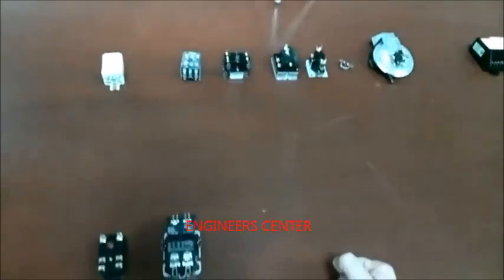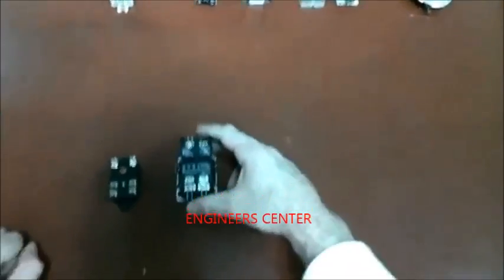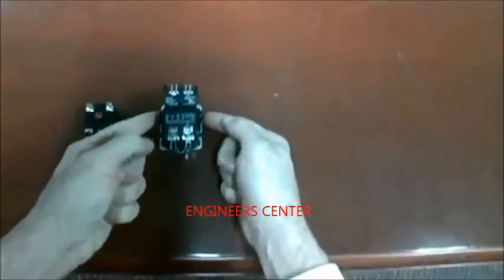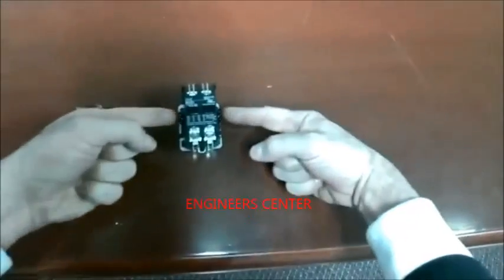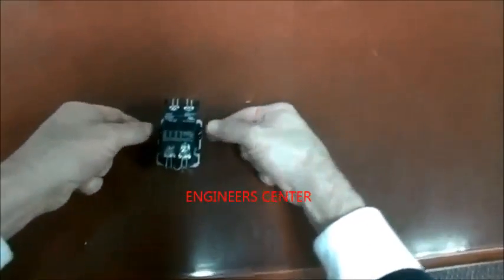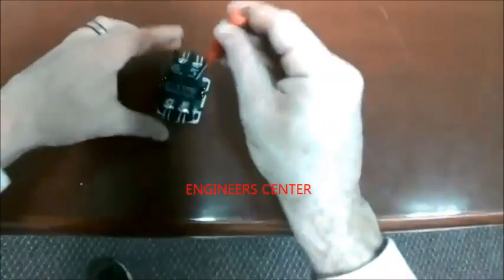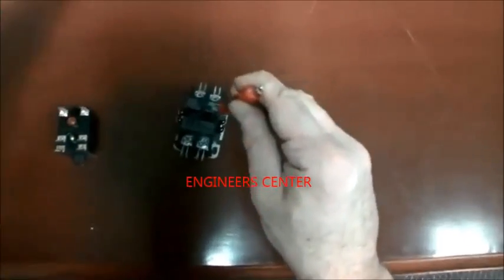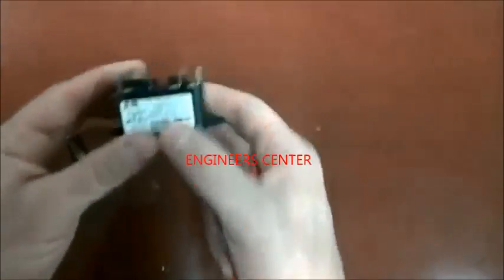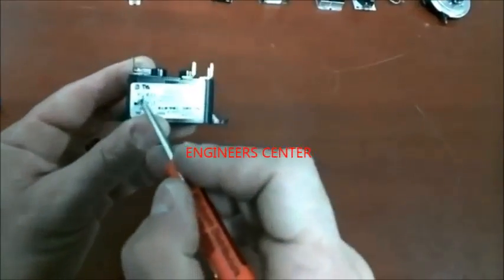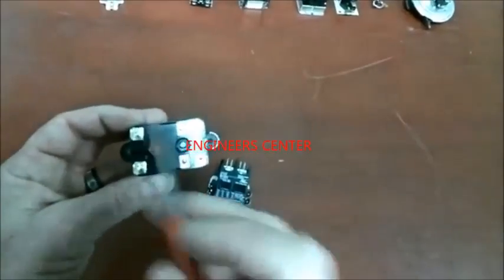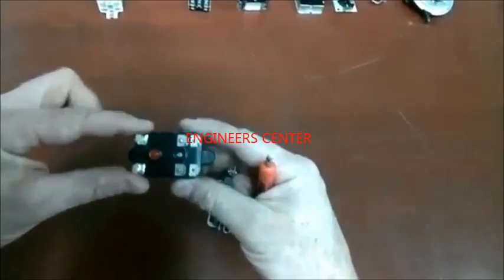What differentiates these types of relays is what tells them to open or close. So this contactor is told to close by getting a signal of 24 volts to the coil here, which will then close the contactor, sending power to your components. The relay would in fact do the exact same thing.